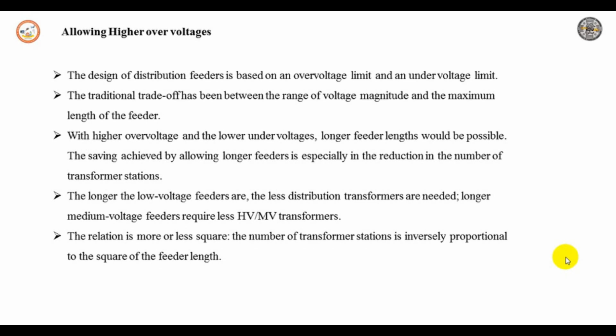The design of distribution feeders is based on the over voltage limit and the under voltage limit. There is a traditional trade-off between the range of voltage magnitude and the maximum length of the feeder. With a higher over voltage limit and a lower under voltage limit, a longer feeder length would be possible. The saving achieved by allowing longer feeders is especially in the reduction in the number of transformer stations.